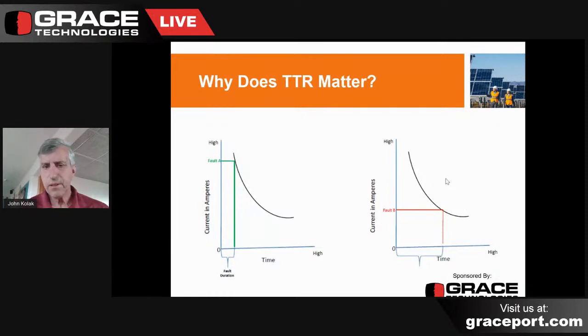What we're trying to do here is that this curve you see is a rough estimation of what a time current curve for a fuse would look like. It's an inverse time fuse, as you can imagine. So here we see if we have very high fault current in the system, the fault clears on the x-axis here is the time, the clearing time. The y-axis is the fault current level, the short circuit current. So you see if we have very high fault current, the clearing time is relatively brief. Take the same curve and have much lower short circuit current, meaning a higher impedance fault in the system. This translates to much higher incident energy levels. Let's go to the next slide.